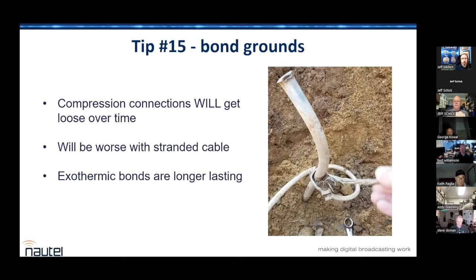So yep, I'm a huge fan of exothermic connections, whether it's brazing, Silphos, or silver solder to a lesser extent. CADweld, love CADweld. You can even buy CADweld molds on Amazon now. You specify what you're bonding to what, touch it off, and bang, you're done, it's permanent. So absolutely, whenever you can, use an exothermic connection, whether it's brazed or a ground strap. If you fold a ground strap to make an angle, braze or solder it. Brazing a ground strap can be tricky, but solder it at the very least at the fold, otherwise you end up with an inductor once it oxidizes a bit.